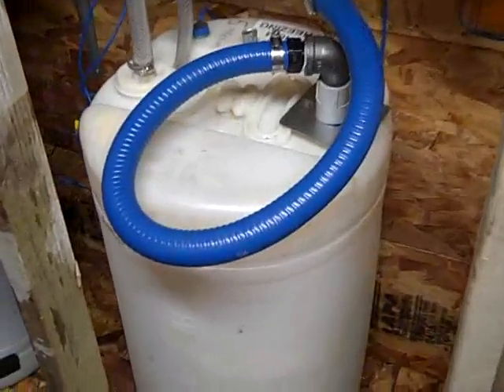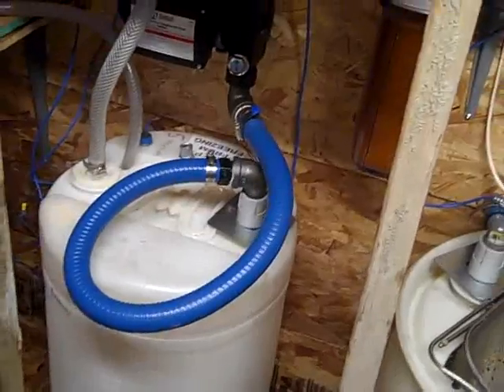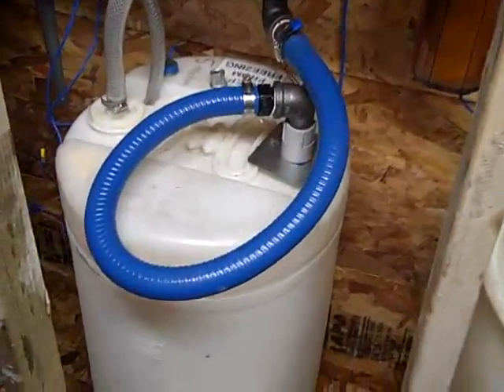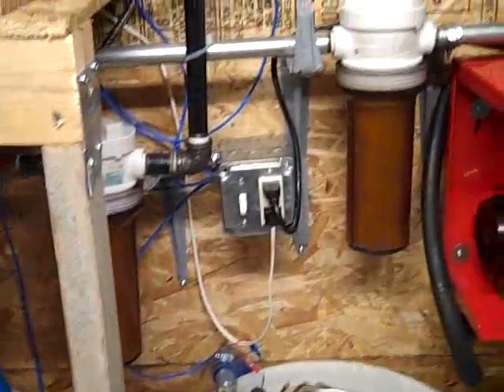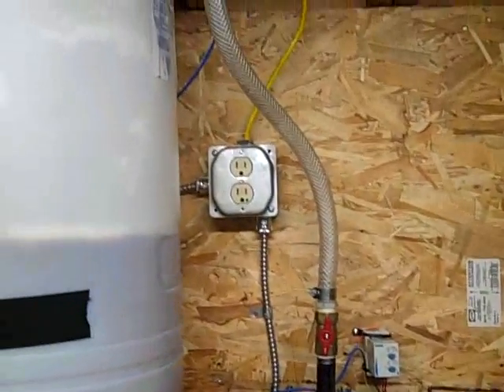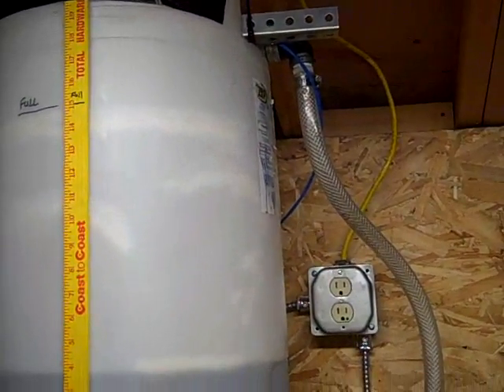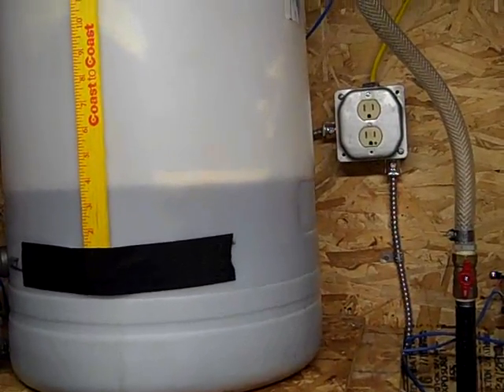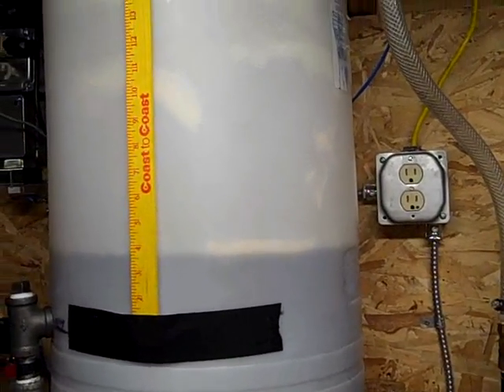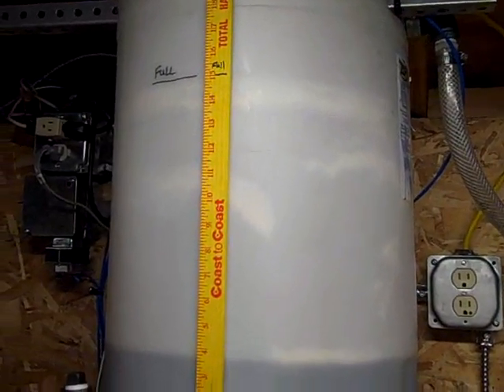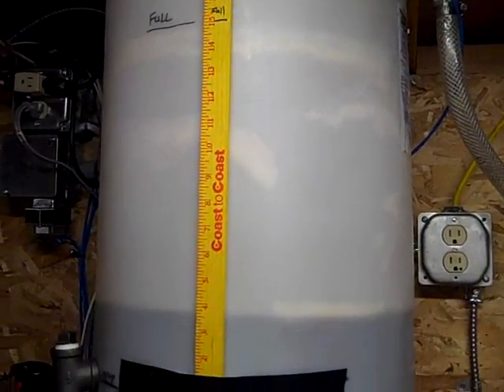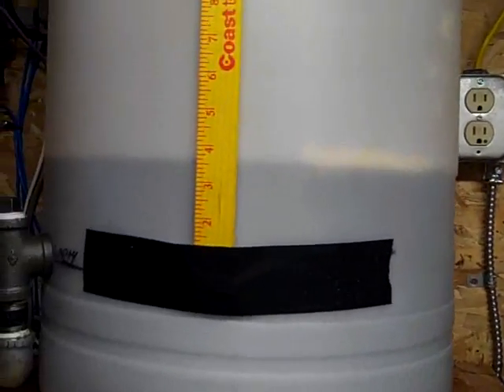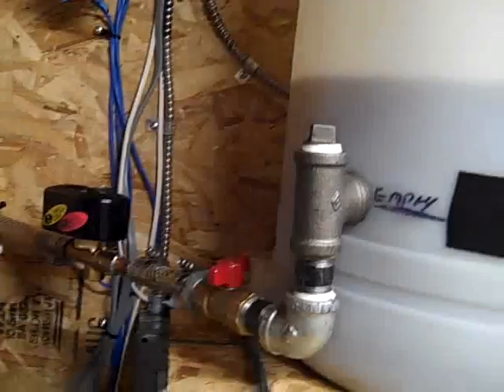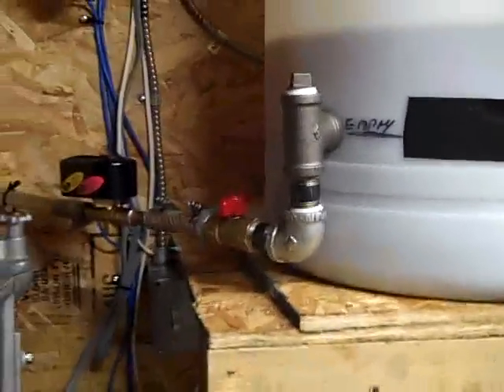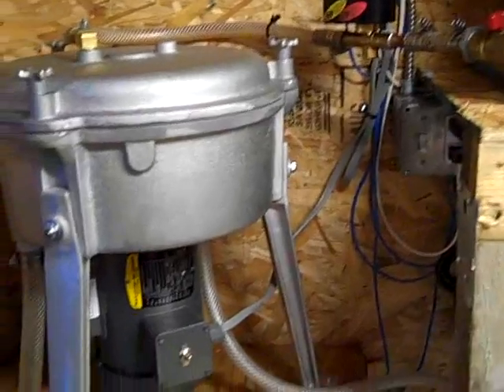In this barrel we have a float control also for when the barrel does have oil in it. It turns the second pump on, and it pumps through a filter system there and up into the gravity barrel. This gravity barrel also has a high level float, so that when it gets full it will turn that second pump off, so that we don't have any floods or overflowing of any barrel. From this gravity barrel we have another float system which will turn the centrifuge on. There's the centrifuge.